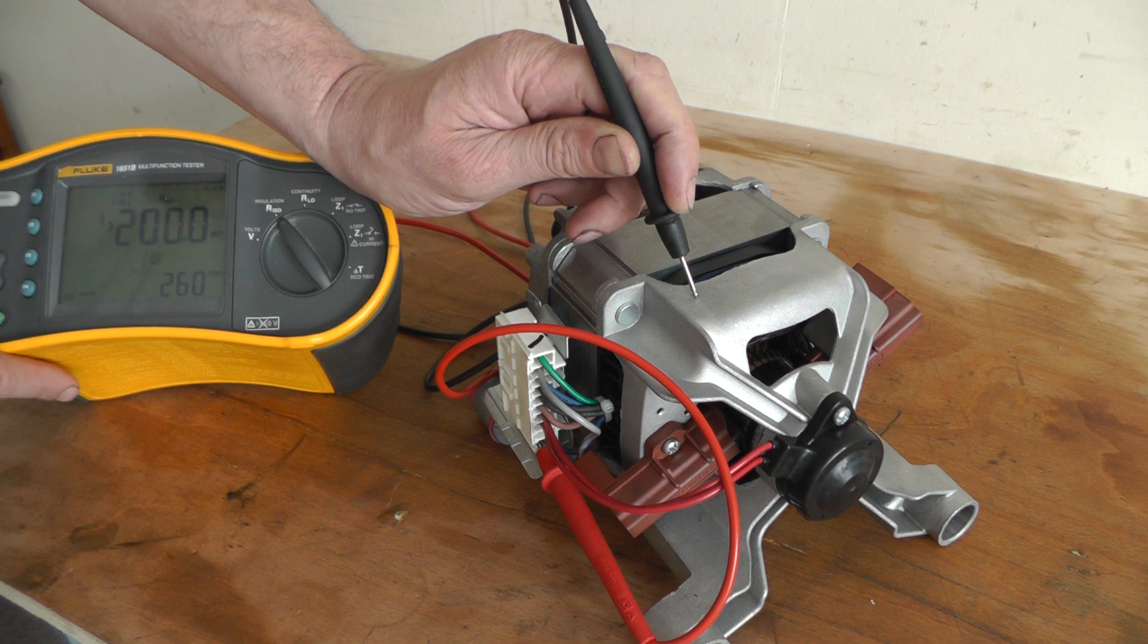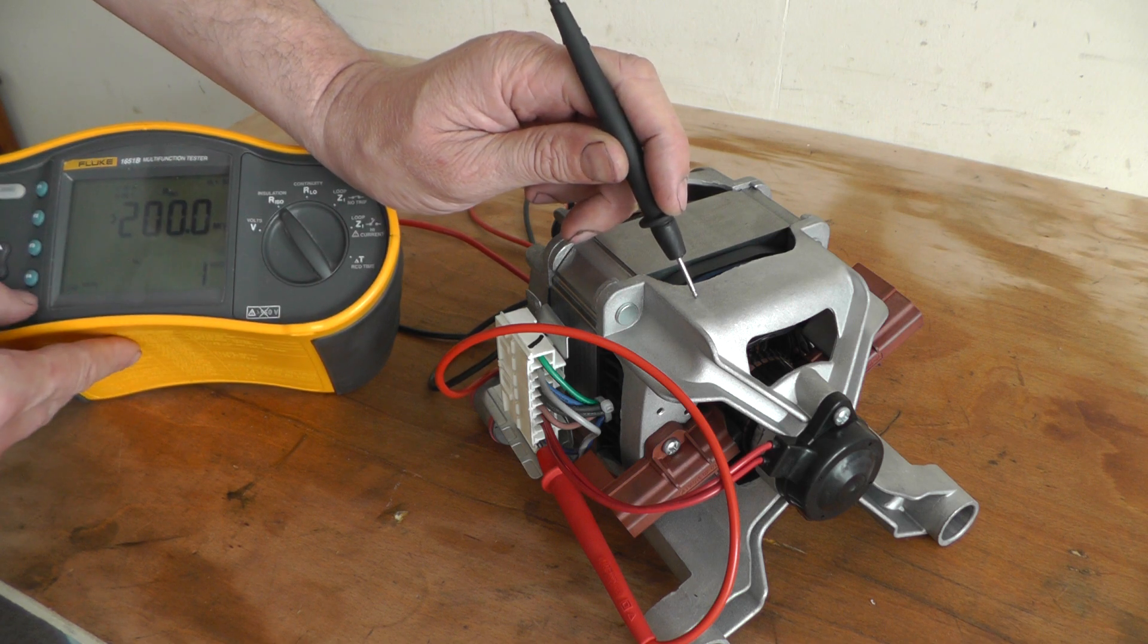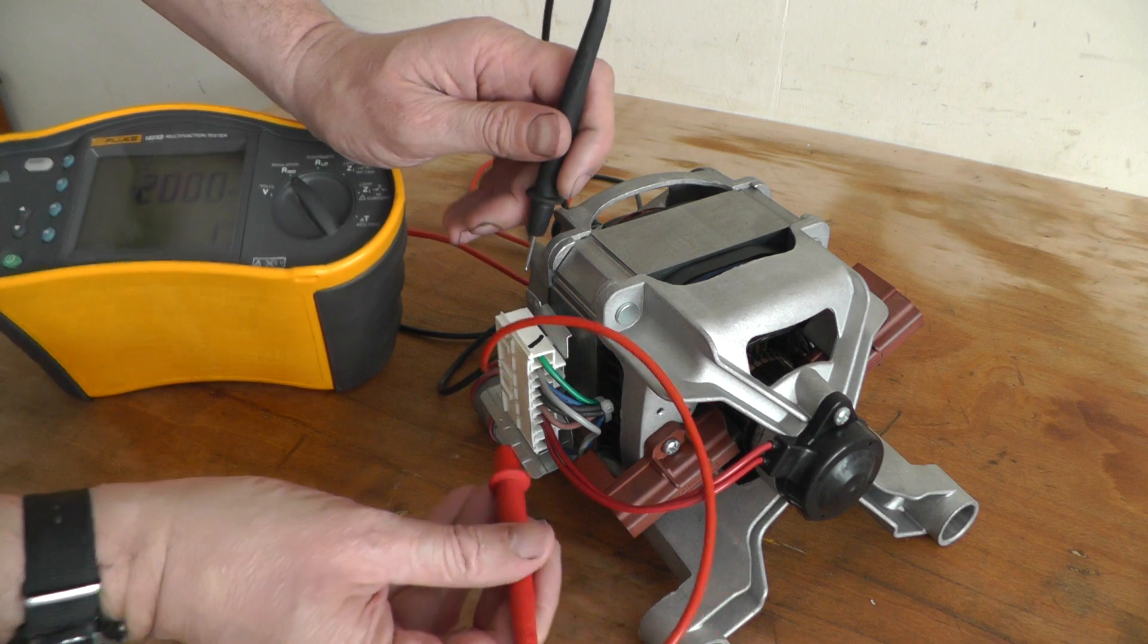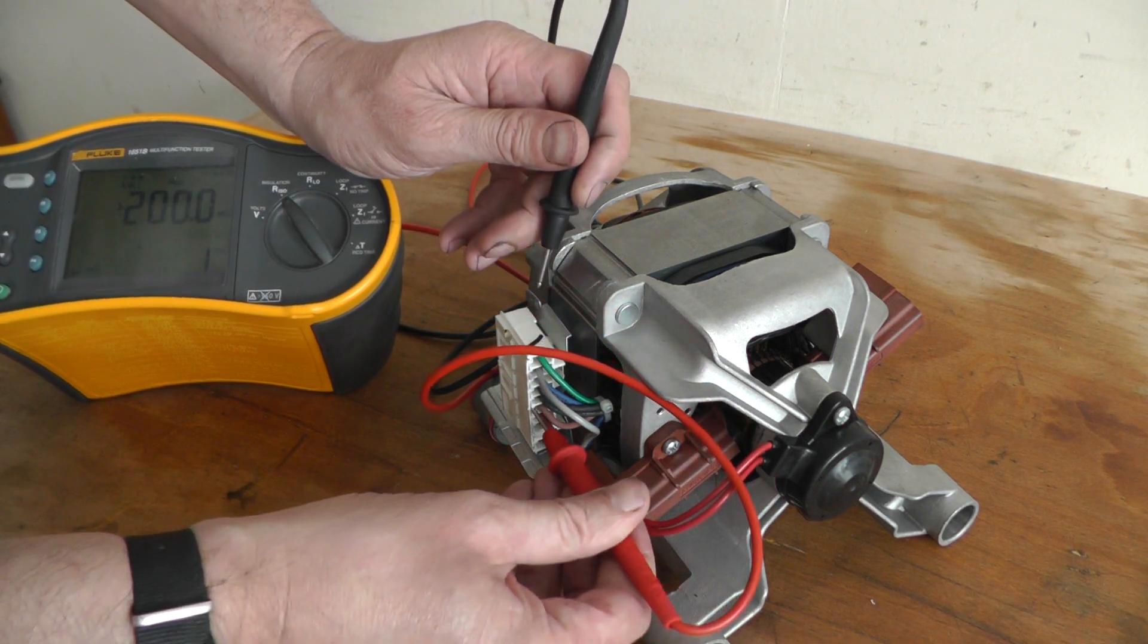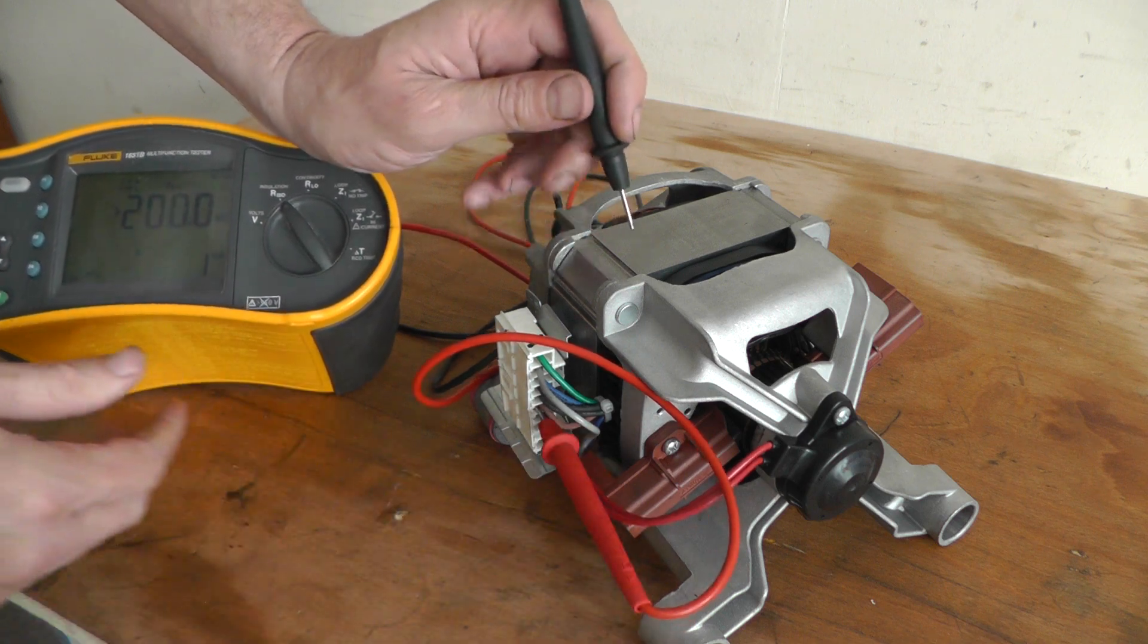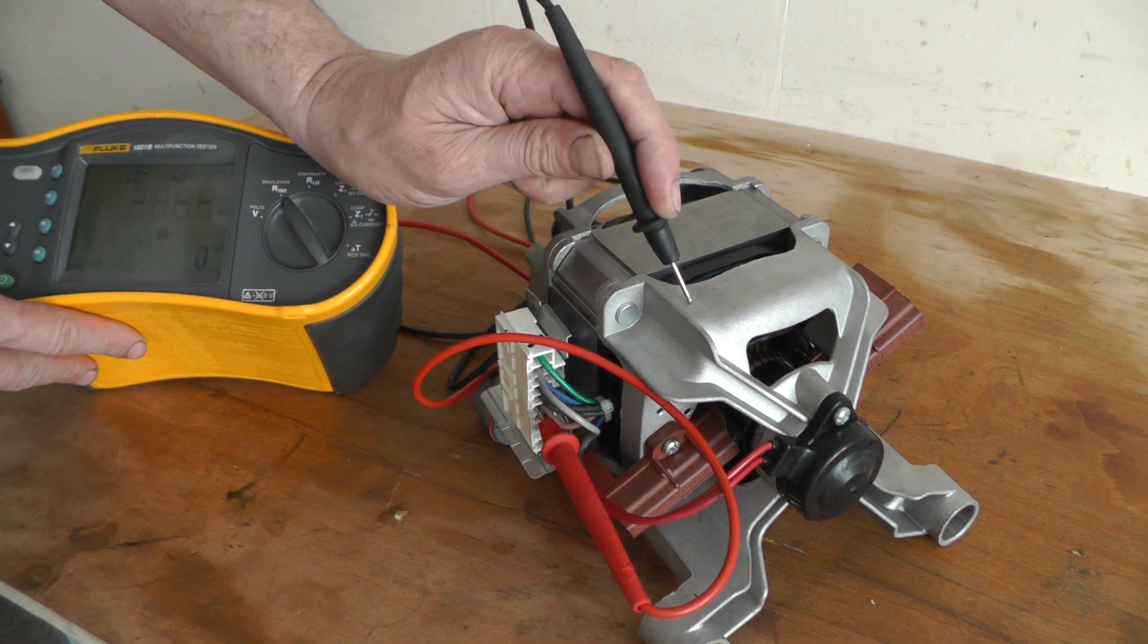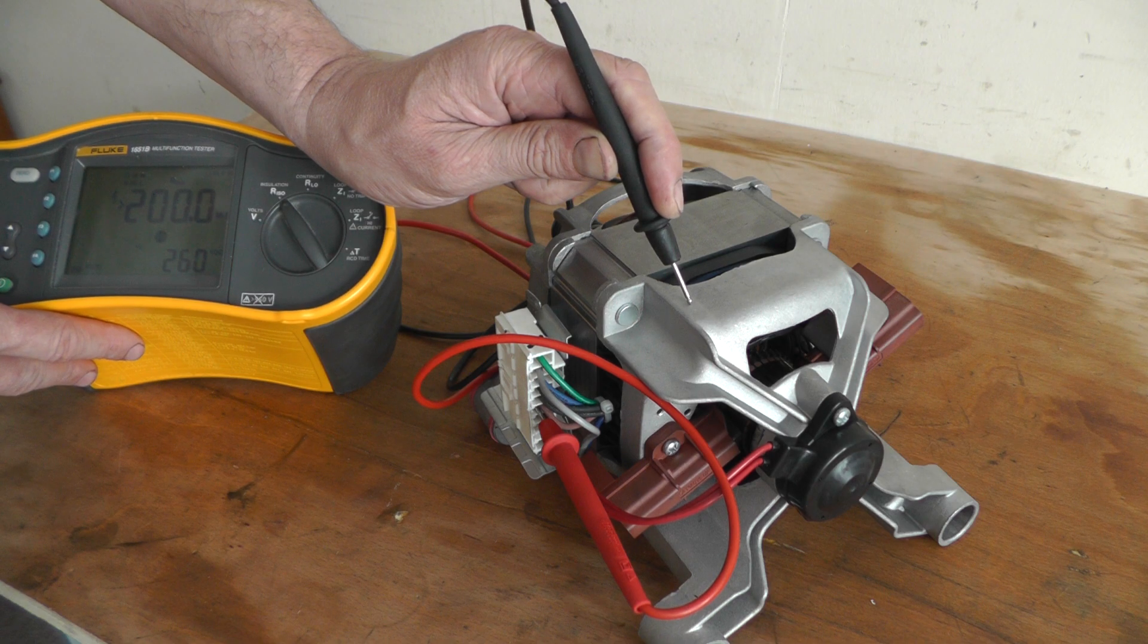So greater than 200 mega ohms at 250 volts. Will do all three windings. You don't want to be touching the chassis when you're doing it or you'll get a little shock.